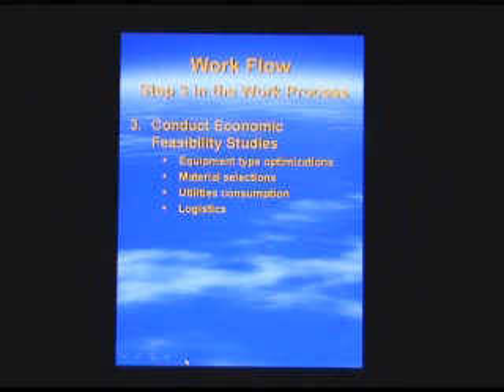We'll conduct feasibility studies. In some cases there may be more than one way to perform a process scheme. We might look at shell and tube exchangers using a utility cooling loop, or we might look at an air cooler loop. With shell and tube exchangers, generally we're conserving energy, whereas with air coolers we're rejecting heat to the atmosphere, so it cannot be recovered. There's also utility costs with respect to the electrical load from the coolers.